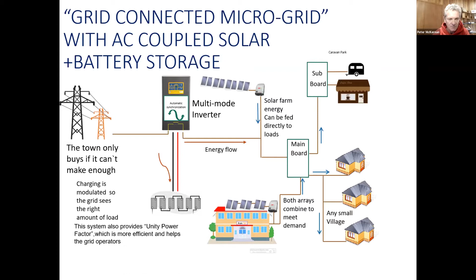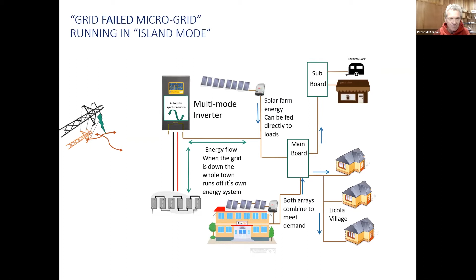From time to time the grid goes down and things don't work. In a situation like that, this small town would operate in island mode, meaning no connection to the grid whatsoever. The contactor lifts internally in the multi-mode inverters, and all of the energy either goes into or out of the batteries according to the town's needs.